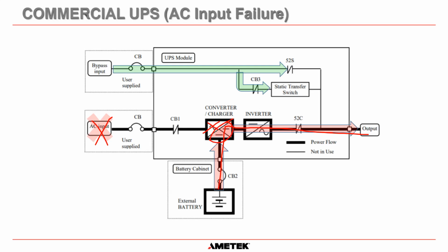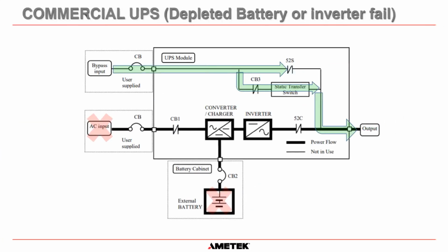Now, once again, in a commercial UPS, remember, there's a DC to DC converter inside that system. So it's taking this 480 volts and it's actually increasing it to about 600 volts going into the inverter. And that's electronic. And in some circumstances, electronics are the first things that fail over time. So it does introduce a mode of failure there with that DC to DC converter. And then if the batteries get to their end of life and the battery depletes and the AC doesn't come back on again, then the static transfer switch will turn on and will put the power to the load that way. And then instantaneously, it will then pull in contactor 52S and it will power the load through that contactor and the static switch will turn off. That is how the commercial UPS works when power fails.